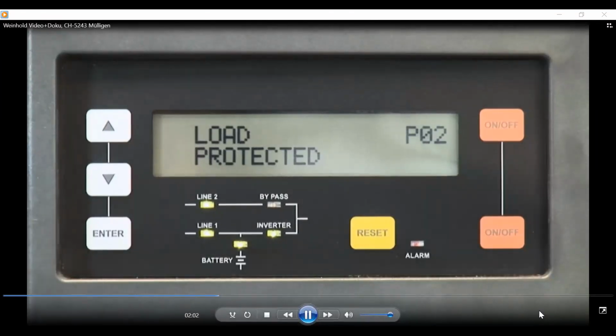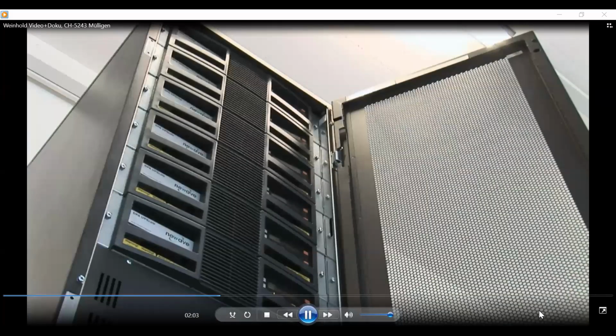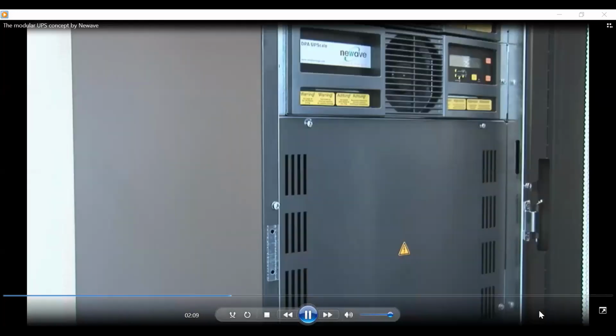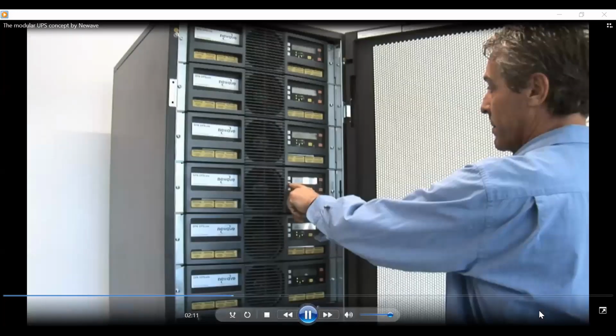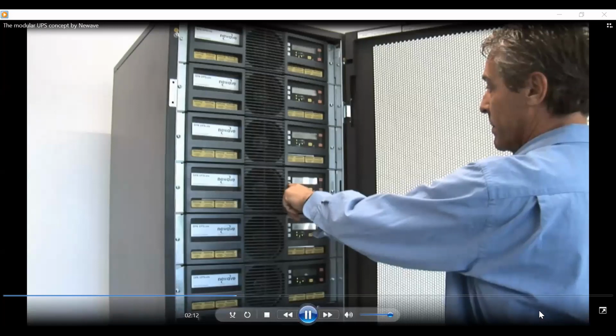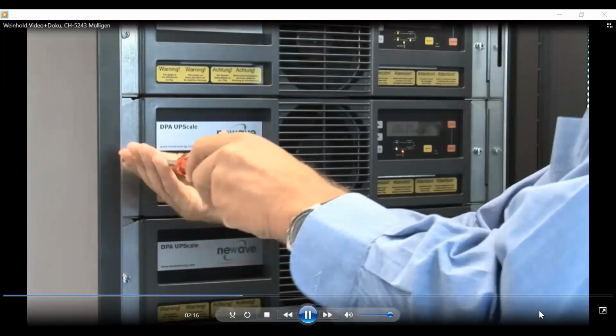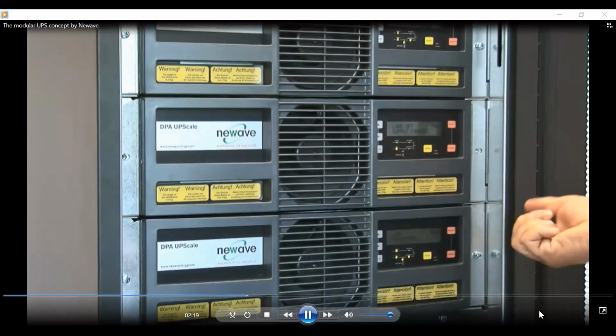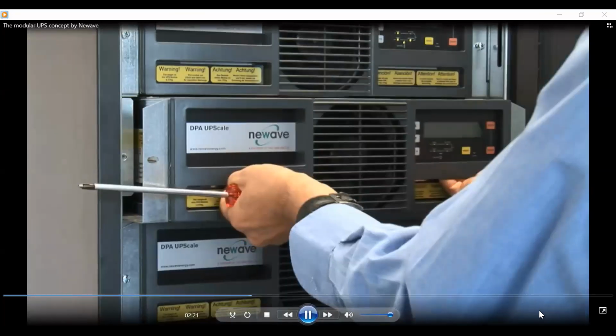System availability is further maximized by the true safe swap modularity of the modules. True safe swap modularity enables the safe removal or insertion of UPS modules without risk to the critical load, and without the need to either transfer the critical load onto raw mains or remove power from the critical load.